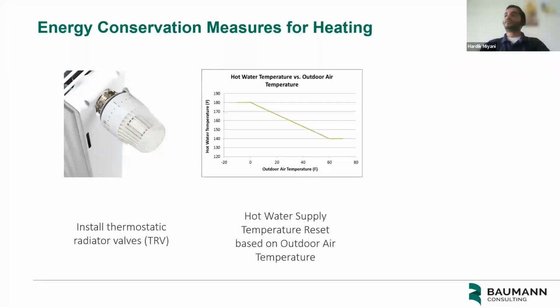Next is the hot water supply temperature reset based on ambient temperature. For the majority of the hot water equipment in the DC market, we are seeing that they provide hot water at a constant temperature throughout the year. Even when the demand for hot water is very low, during the warm months, it is supplying hot water at a higher temperature. So by changing the hot water supply temperature based on ambient temperature, it can help you save energy.